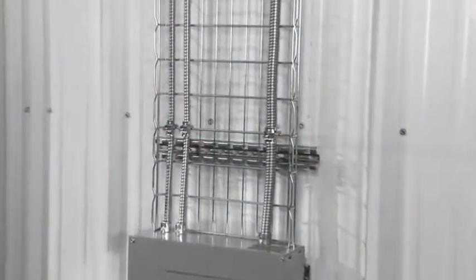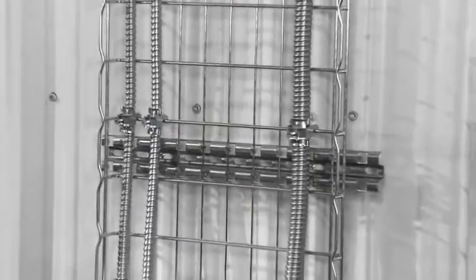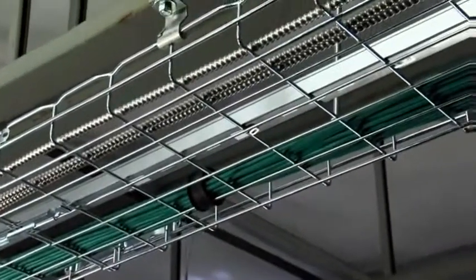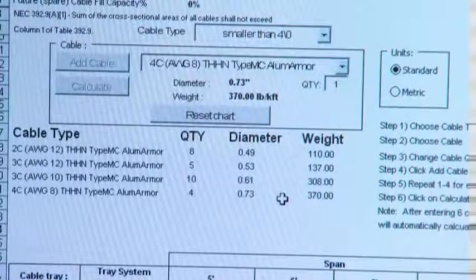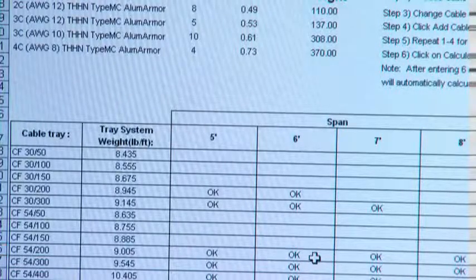Cablofil is capable of supporting all types of cable, from the heaviest MC power cables to a single data cable. In some cases, power and data cables can be run in the same tray by using a metal divider strip to separate them. To determine the combined load, refer to the Cablofil online load table to verify the maximum number of cables your installation can support.